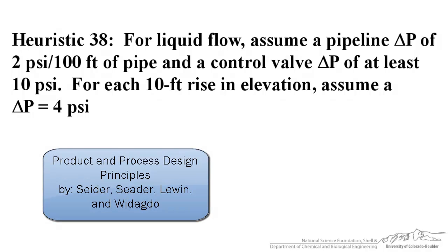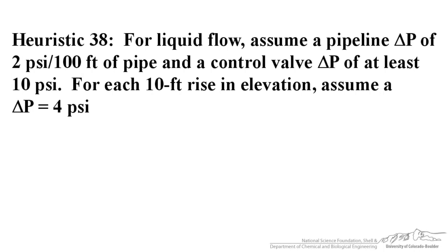In the Product and Process Design Principles book, we're specifically going to look at Heuristic 38, which states that for liquid flow, we assume a pipeline change in pressure of 2 psi per 100 feet of pipe and a change in pressure of at least 10 psi for each control valve. Also, for each 10-foot rise in elevation, we assume a change in pressure of 4 psi.